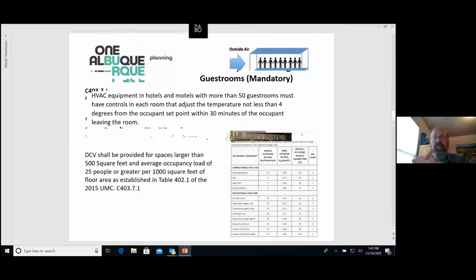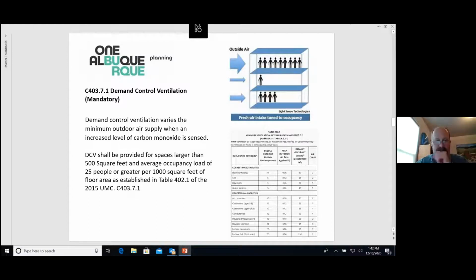So demand control ventilation. Simplified, the more people, the more outside air, as illustrated in the little picture in the upper right. The fewer people, the less you need. This is typically sensed with a carbon monoxide type of sensor that will automatically sense when more is required, and less is required. And depending on the size of the room, if larger than 500 square feet, occupancy load of 25 or greater per 1,000 square feet, the table on the right tells you what percentage or cubic feet per minute you're going to need.